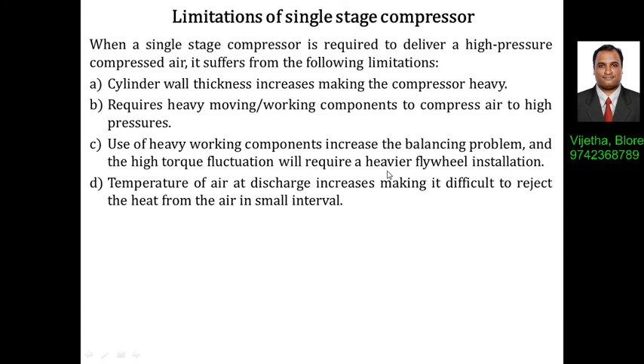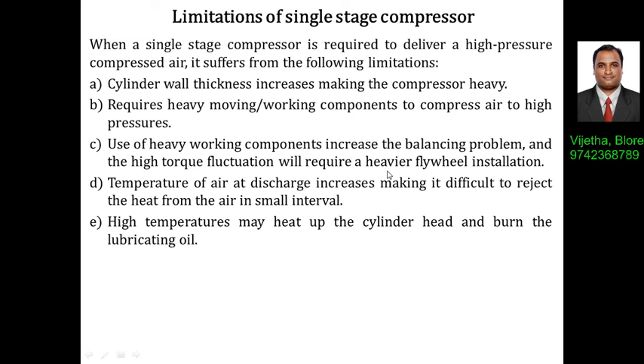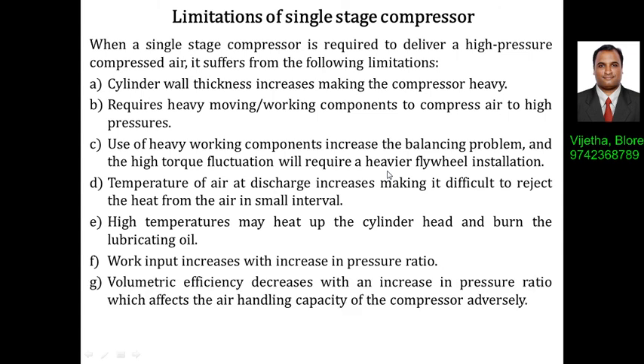Additionally, the temperature of the air at discharge increases, making it difficult to reject heat in a short interval, which may cause seizing of components. High temperatures can heat up the cylinder head and burn the lubricating oil. Work input increases with increasing pressure ratio, and volumetric efficiency decreases with increasing pressure ratio, adversely affecting the air handling capacity — the FAD drops drastically. To overcome these limitations, we will discuss multistage compressors in the next session.